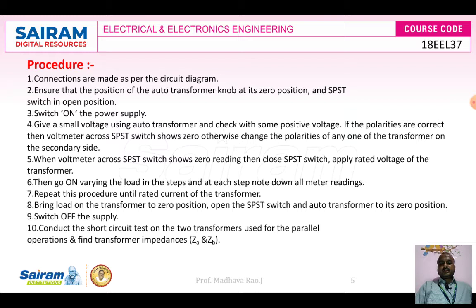Bring the load on the transformer to 0 position, open the SPST switch and set the auto transformer to its 0 position, switch off the supply. Conduct the short circuit test on the transformers used for parallel operation and find the transformer impedances. So ZA and ZB we have to find out.